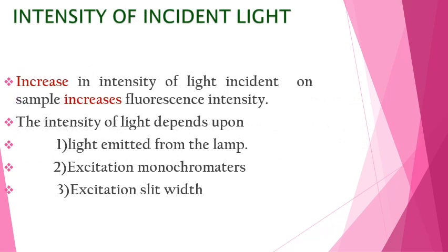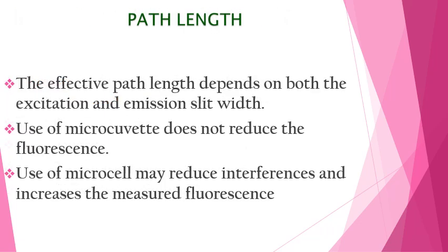Increase in intensity of the incident light on the sample increases fluorescence intensity, and this intensity of light depends on the light emitted from the lamp, the excitation monochromator, and the excitation slit width. The effect of path length depends on both the excitation and emission slit width. Use of the microcuvette does not reduce the fluorescence, while the microcells may reduce interference and increase the measured fluorescence.